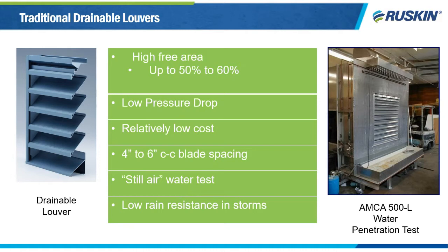And while the open louvers can handle a large amount of air with little rain carryover in still air, they offer little rejection to wind in wind-driven tests. Look at the picture on the left. That louver has a 4-inch blade spacing, and you can almost reach your arm through it. Wind has an easy path through it, and it will carry rain with it. The reality is that with these types of louvers, it may not matter how slow the air is moving through the free area when it comes to rejecting rain. The blades are just too far apart to keep the rain out, even with no ventilation airflow being pulled through it.